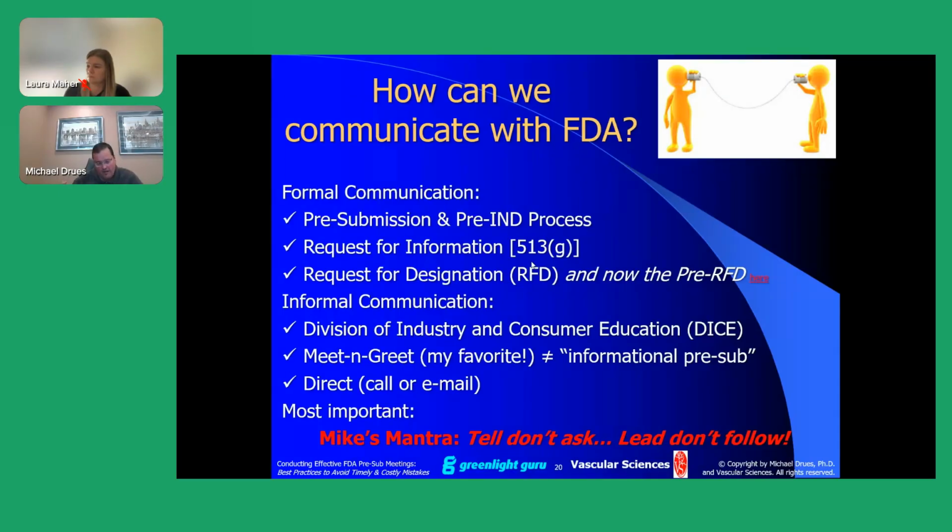Walk into the FDA in your pre-sub and say very confidently, here's my device, this is what it does, here's how it works, here's its mechanism of action, and so on and so on. For all of the following reasons, we're bringing it onto the market as a 510K or a de novo or a PMA, and here's why. For all of the following reasons, here is the testing that we're going to do, and here's why, and here's the testing that we're not going to do, and here's why. And then for all of the following reasons, we're not going to do a clinical trial, and here's why, or we are going to do a clinical trial, and here's what it's going to look like, and so on and so on.